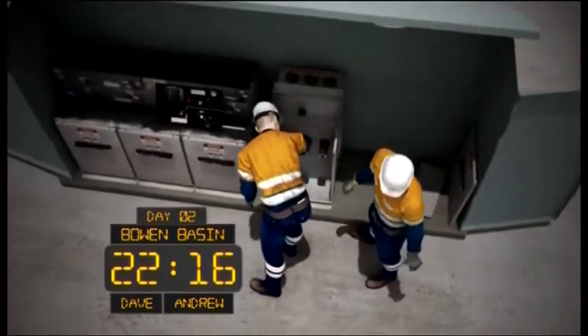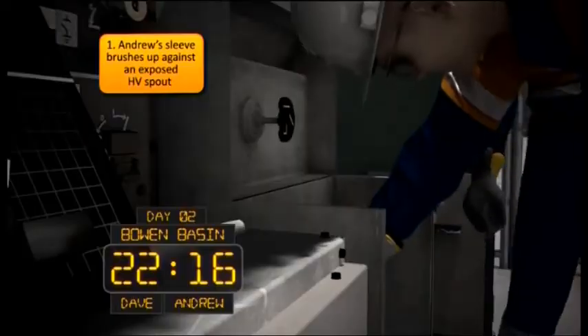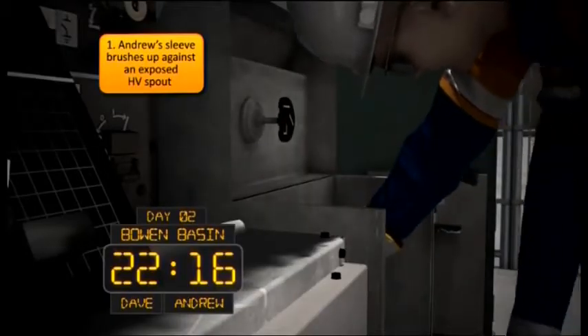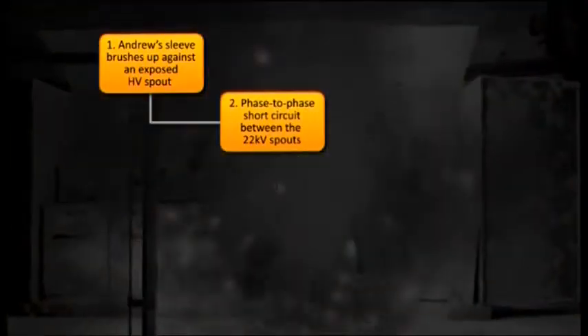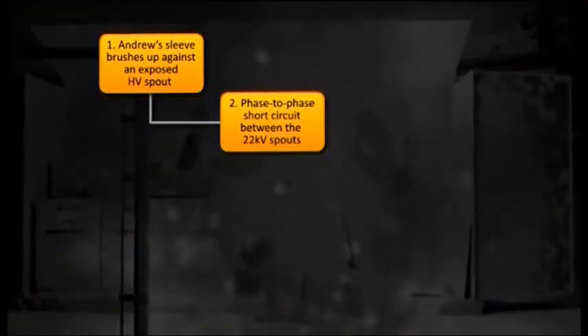What has just happened? What caused the explosion? Let's step it back and try and view this in slow motion from a different angle. We can now see that Andrew's sleeve brushes up against one of the exposed high voltage spouts, creating a phase-to-phase short circuit between the 22 kV spouts.